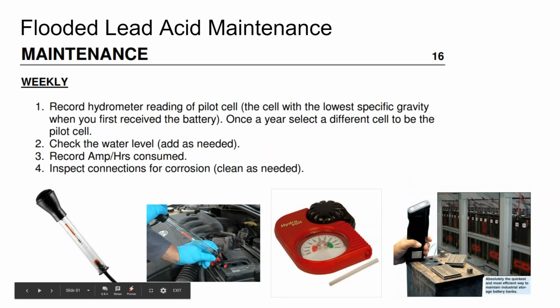In the spring and fall, when your batteries aren't being cycled so heavily, this might spread out to every 2 or 3 weeks rather than weekly. But taking those voltage logs is the tedious, time-consuming part. We're talking about a 15-minute maintenance task that, at its peak during peak season, is a once-a-week task.